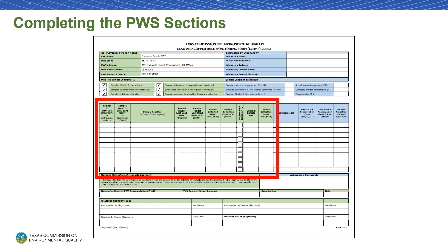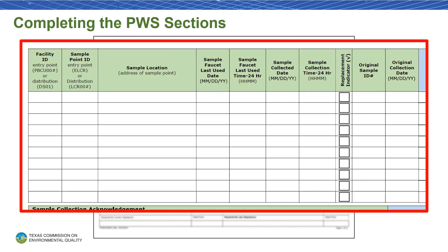Next, let's fill out some information on our samples. In the first column, write the facility IDs for the samples. If a sample is from an entry point, the facility ID should begin with PBCU, followed by the entry point number, which can be found on Drinking Water Watch under the Water System Facilities tab. If a sample is from the distribution system, the facility ID should be DS01. In the second column, write the sample point IDs. If a sample is from an entry point, the sample point ID will be ELCR. If a sample is from the distribution system, the sample point ID will be the LCR number for that sample location.